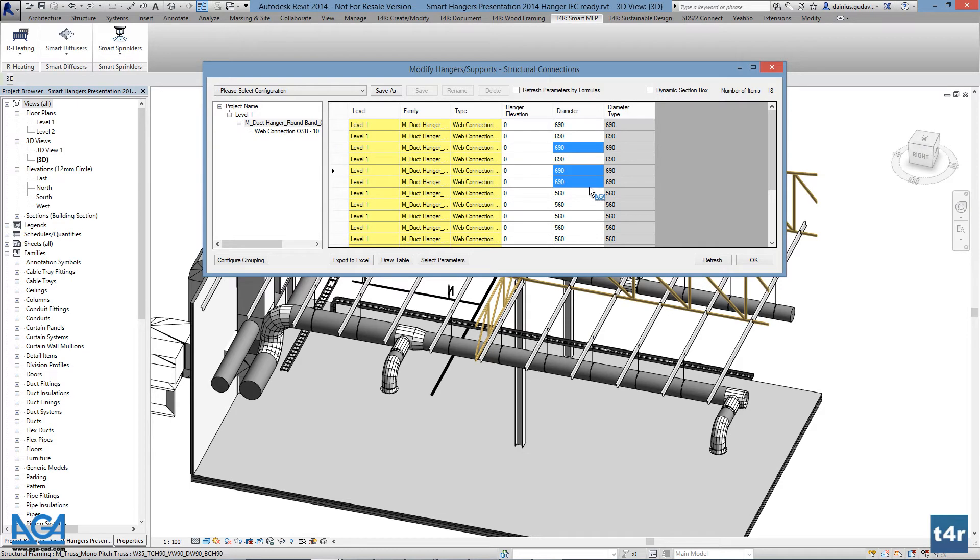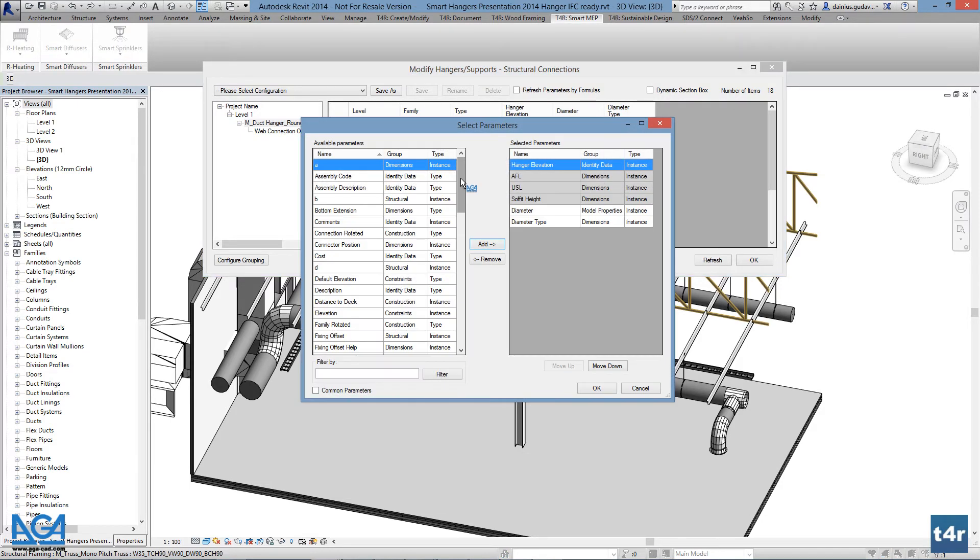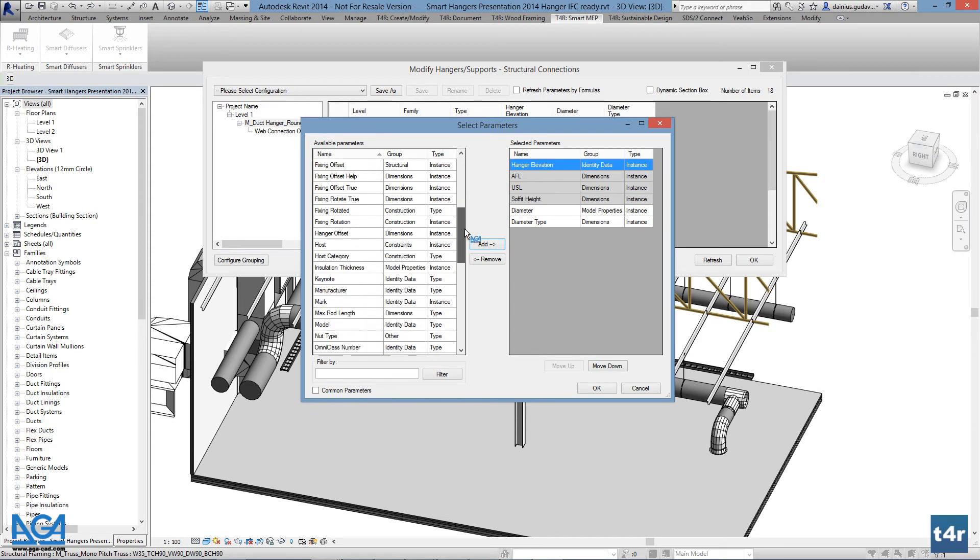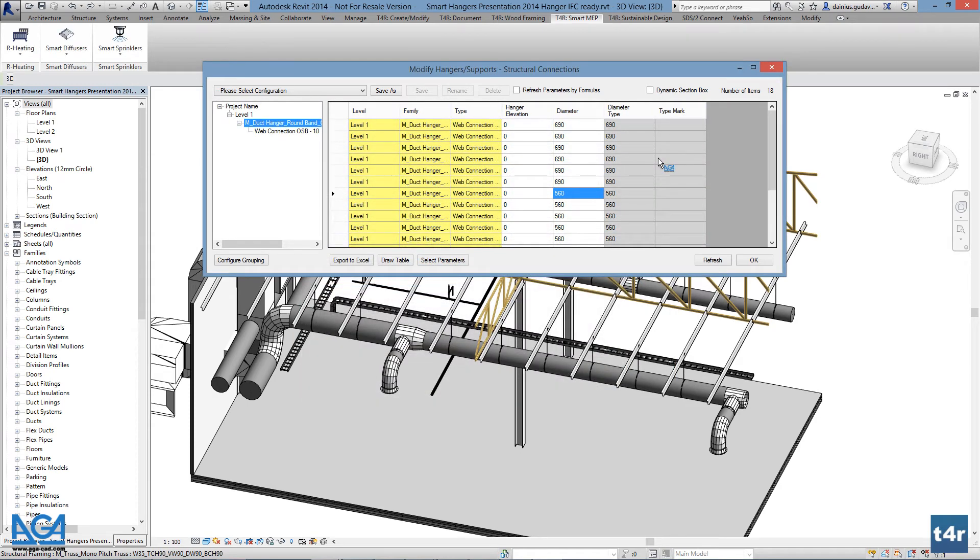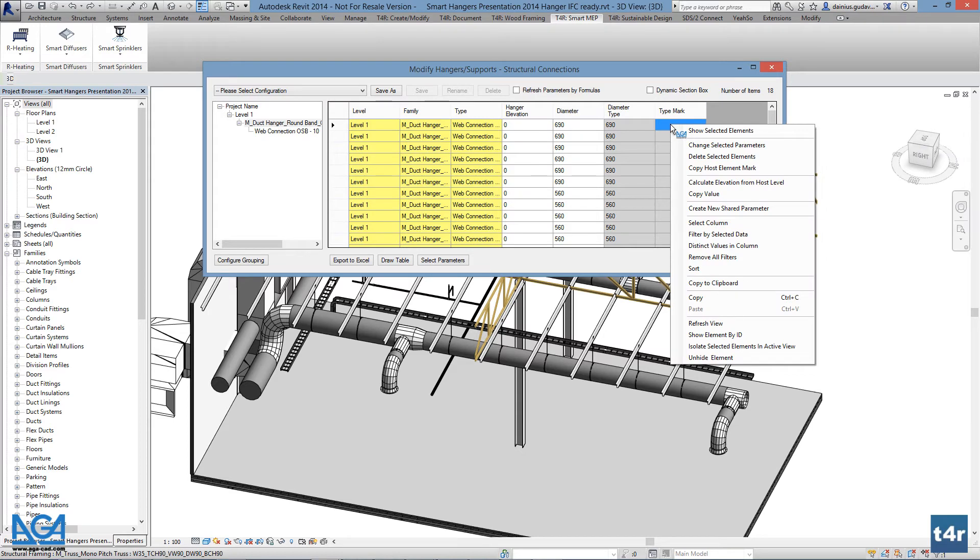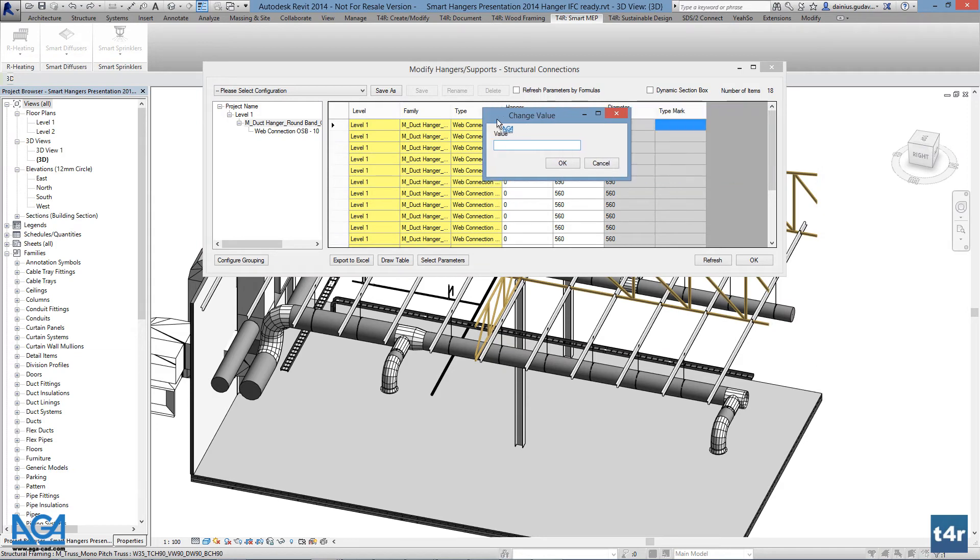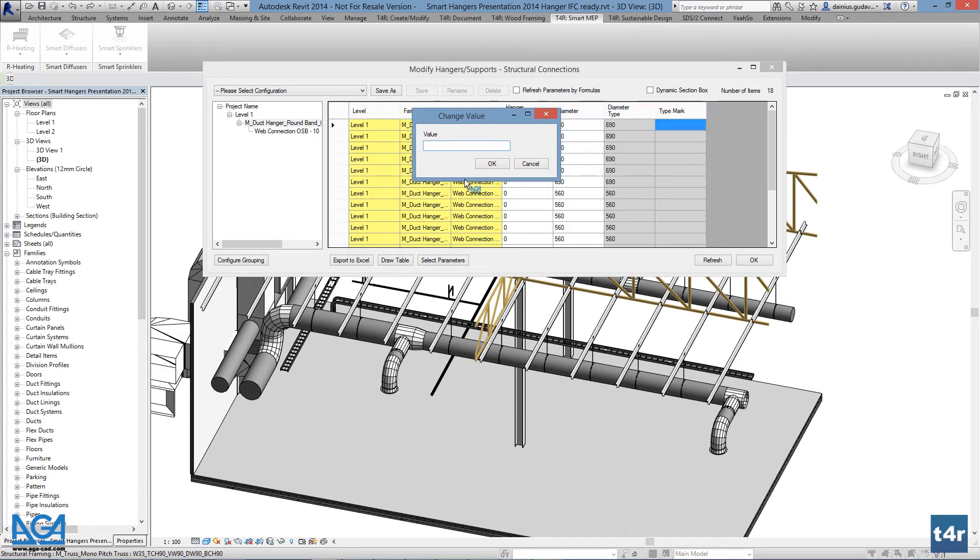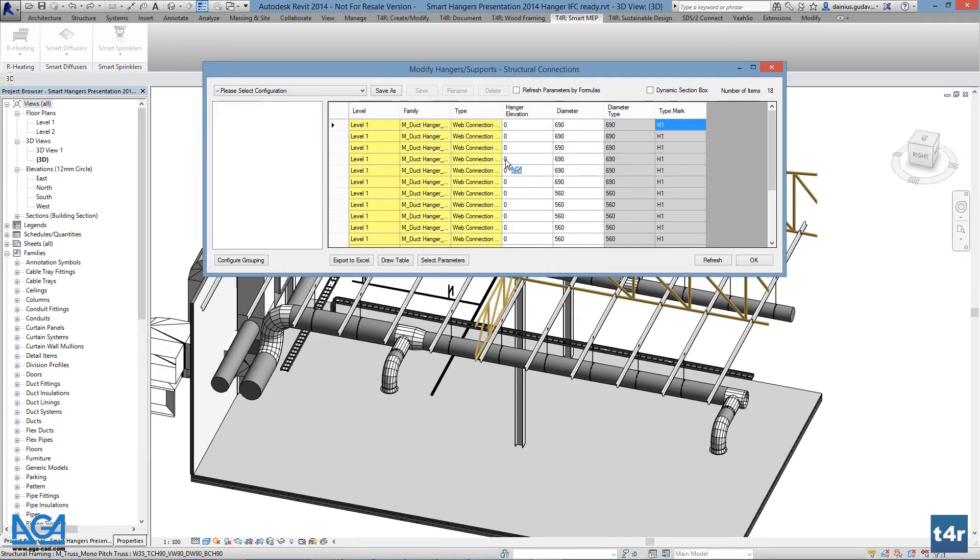Let's add some type mark values for hanger type. Go to select parameter, find type mark, add it to the list, and press OK. Type mark is a type parameter, so the hangers or supports of that type will have duplicate type mark values. Select one parameter and press the right mouse button. After pressing the right mouse button, press change selected parameters and enter a value, for example H1, and press OK. Now all hangers with that type have the H1 value.